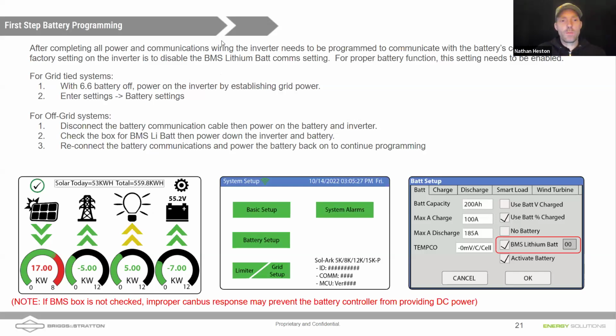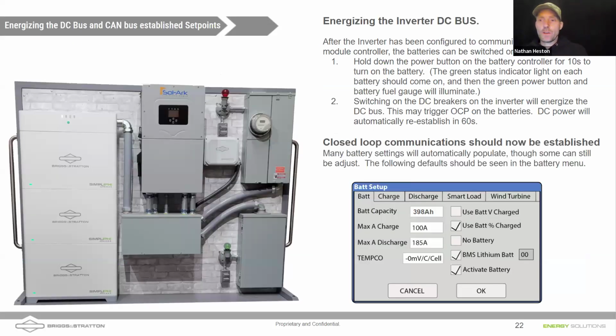We'll reconnect the battery communications cables and go ahead and start with the programming. So that's just a note about getting us started. So once the Sol-Ark inverter is programmed to accept CAN bus communication and to deliver CAN bus communication on the CAN bus channel, we're going to need to start with the programming.